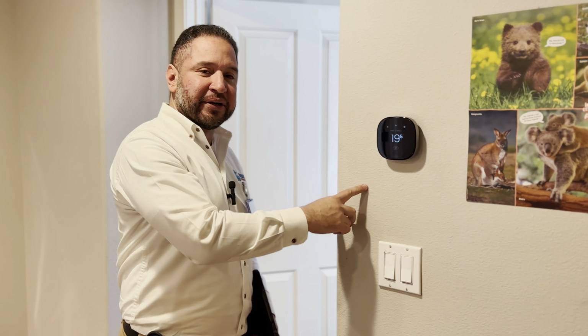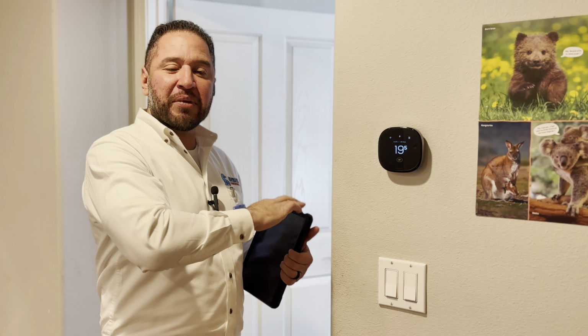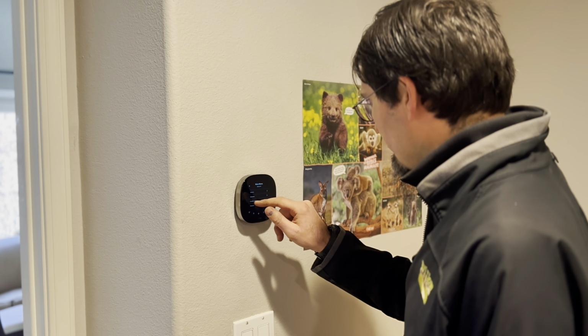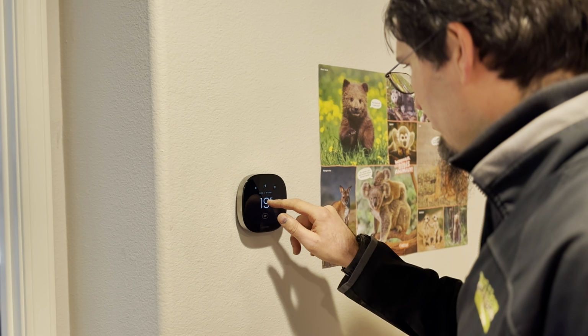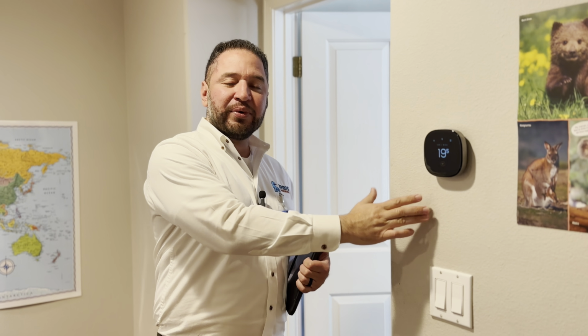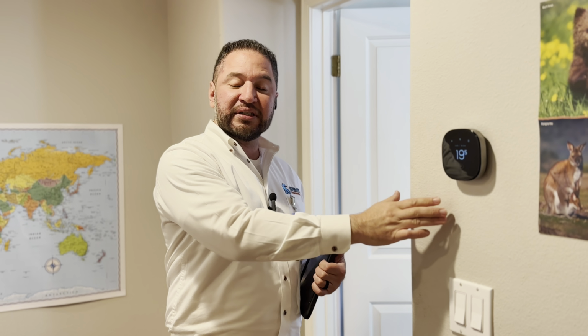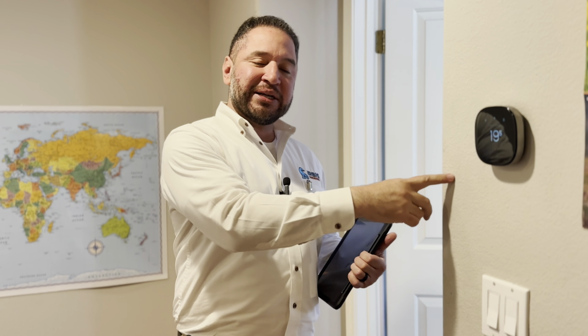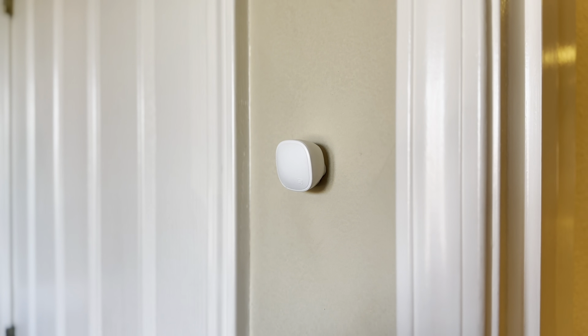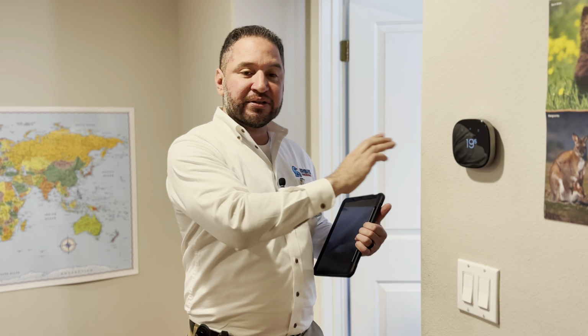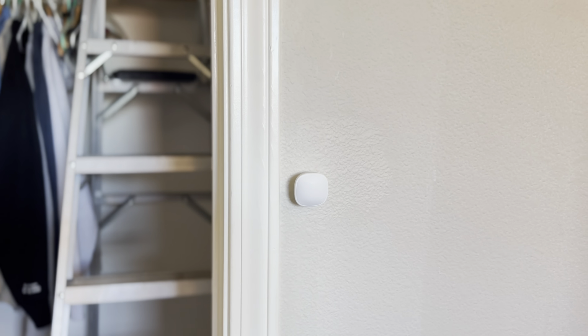If we take a look on the second floor, we have a separate thermostat up here. So this thermostat is monitoring the temperature specifically on this floor. We want to locate it near the return. That's where we're going to get the most accurate reading for the temperature. So now we can provide heating or cooling to this specific area of the home based on the temperature that this is. We're pretty familiar with having room sensors added to this. Well, this is actually being controlled by a zone control panel, which will open and close electronic zone dampers.